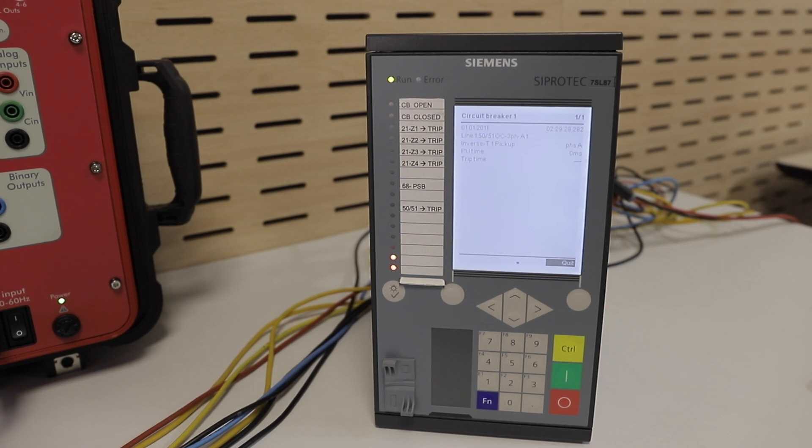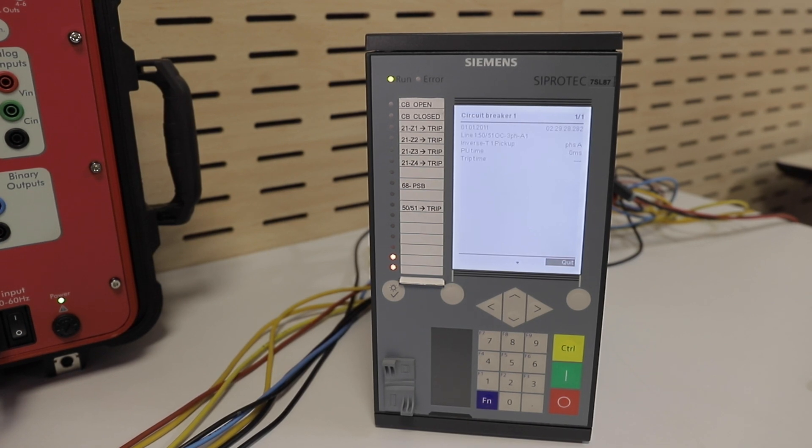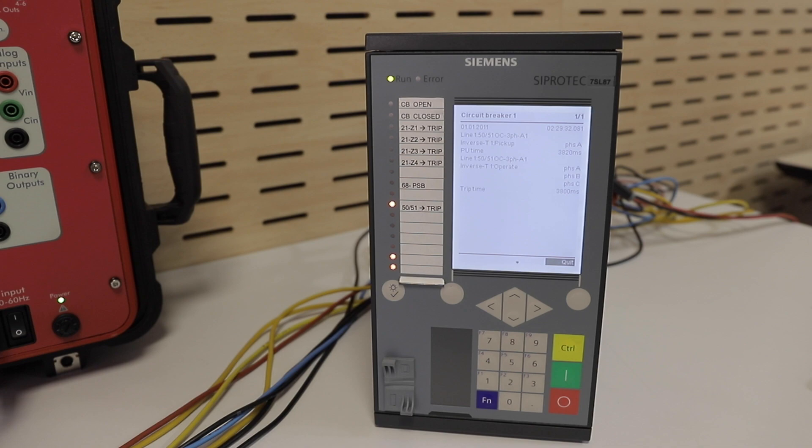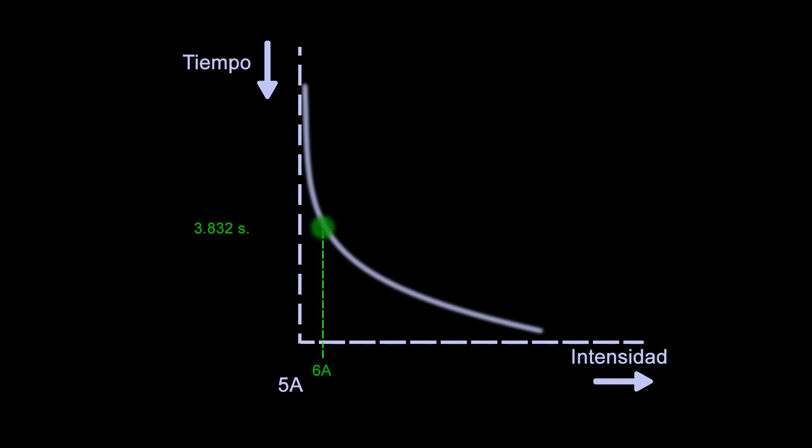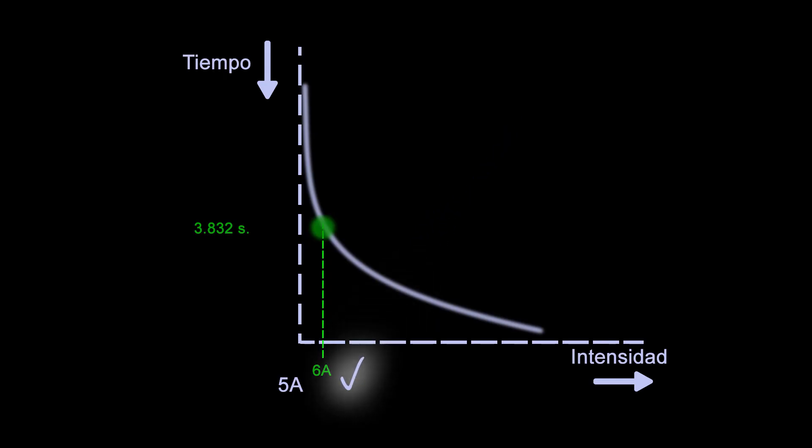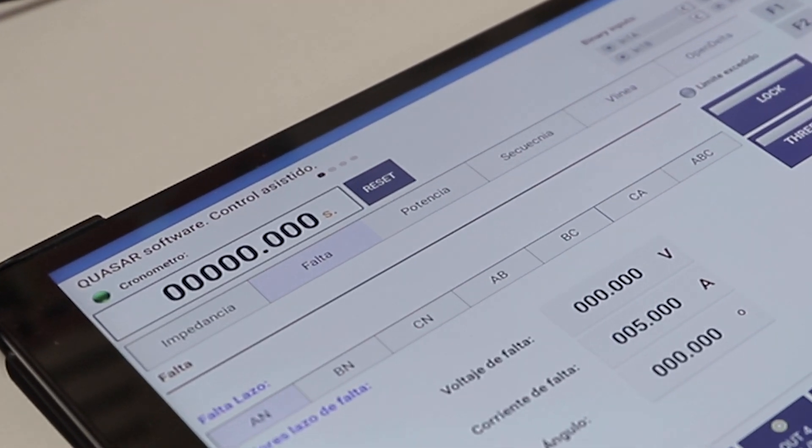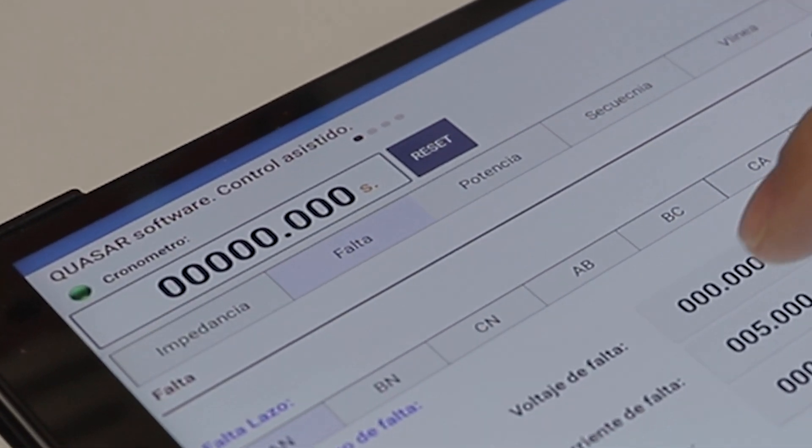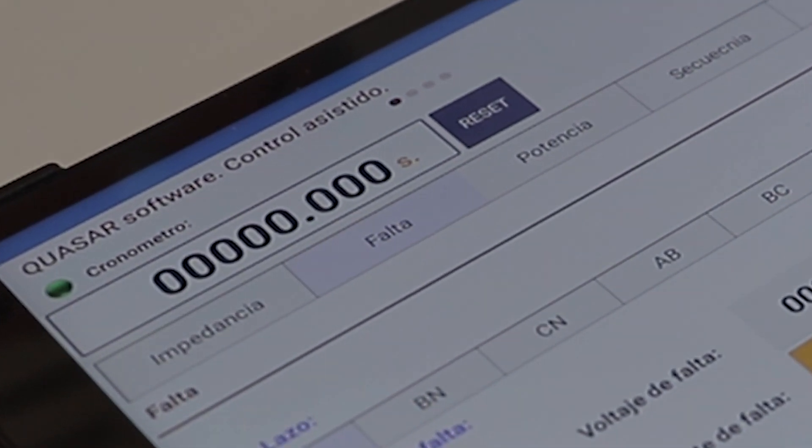As expected, the relay has operated with this current in a time that is virtually identical to the corresponding one in the characteristic curve. Let's repeat the test to confirm these results.